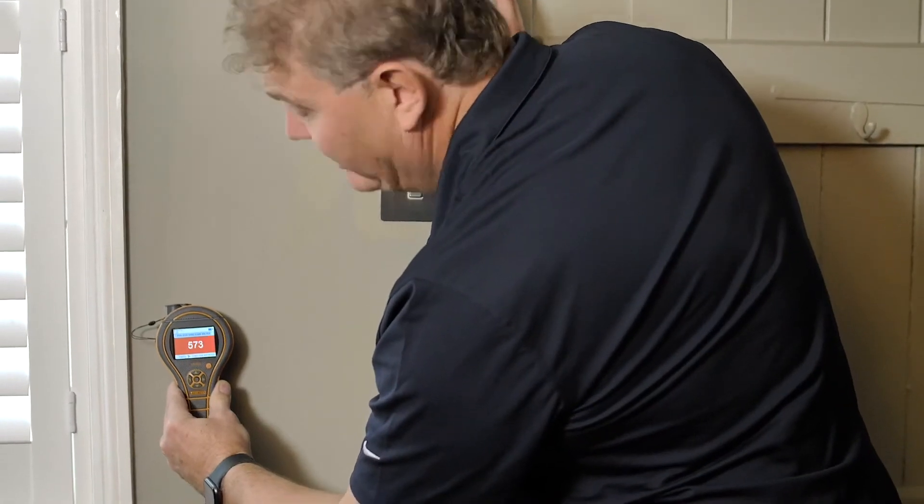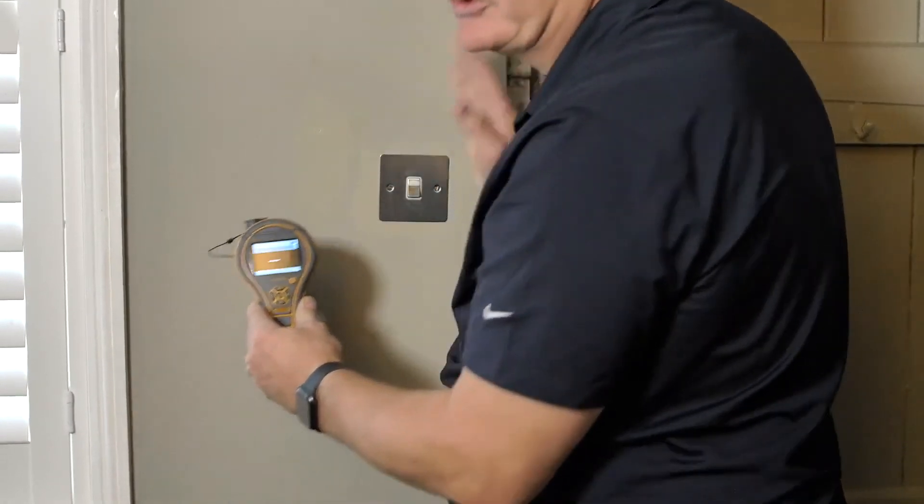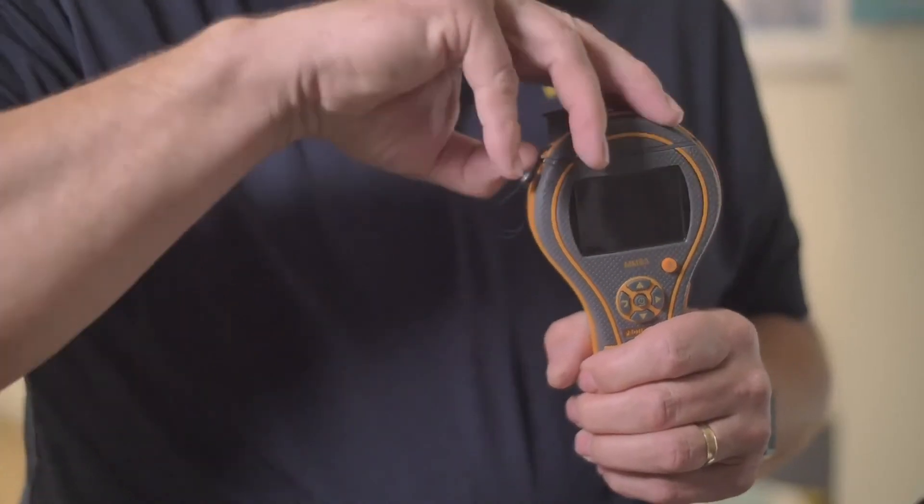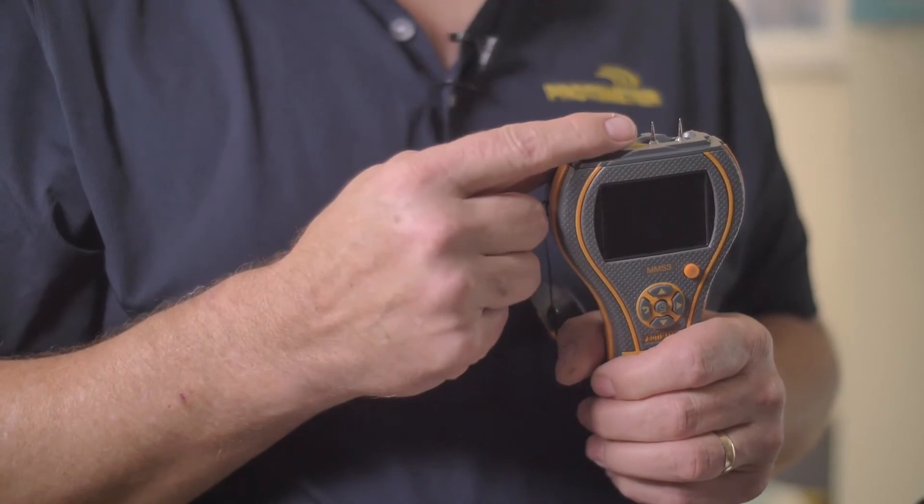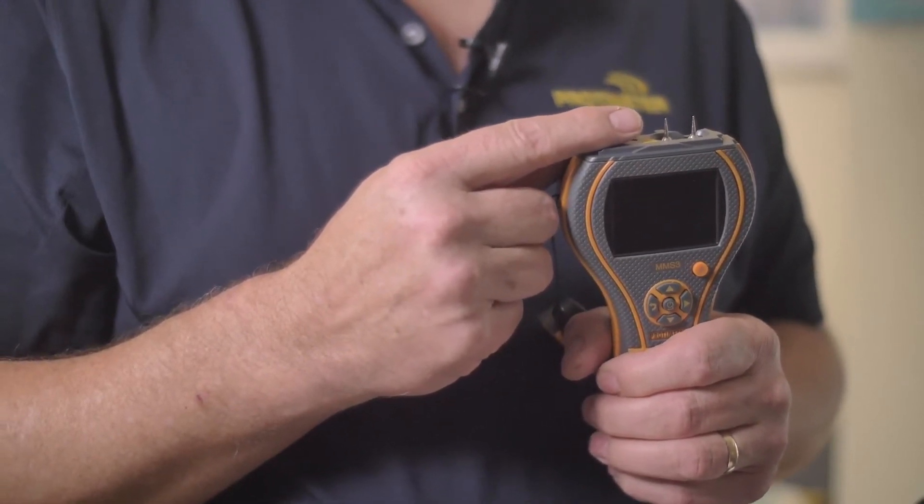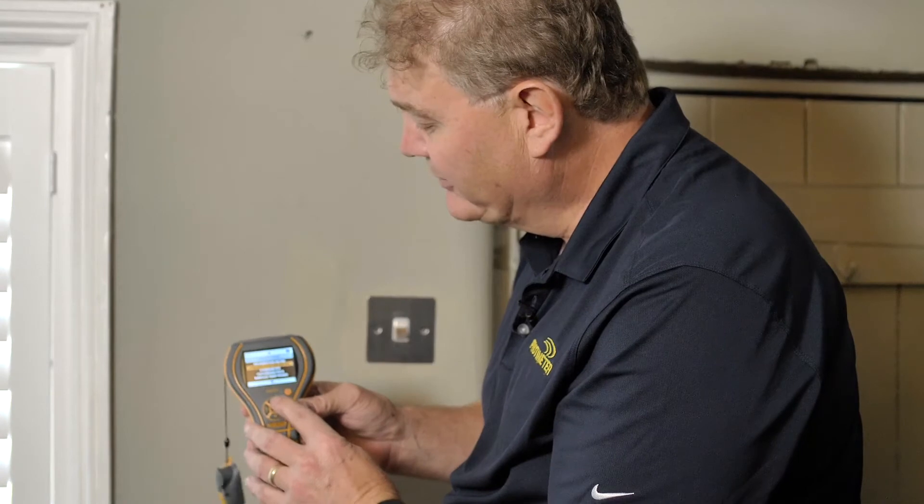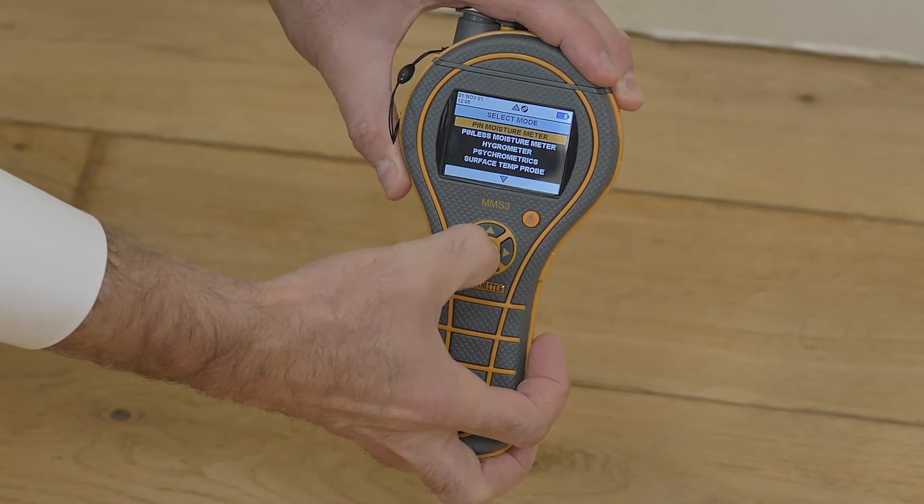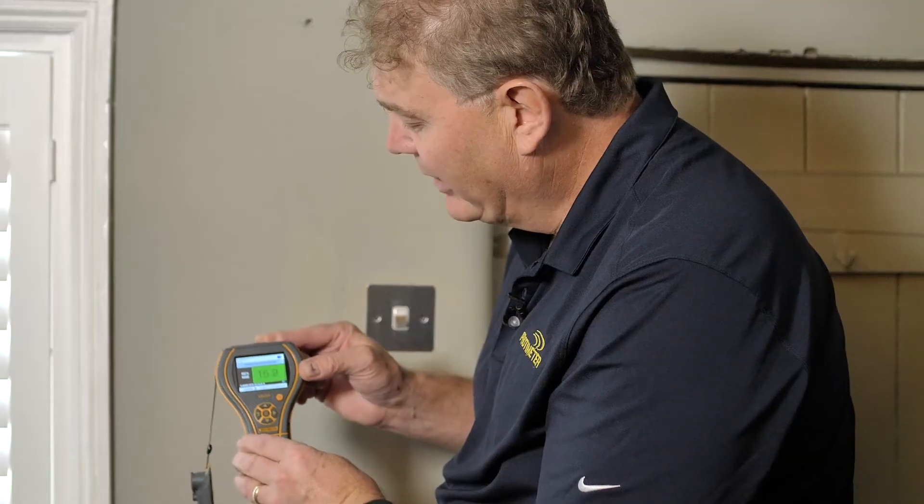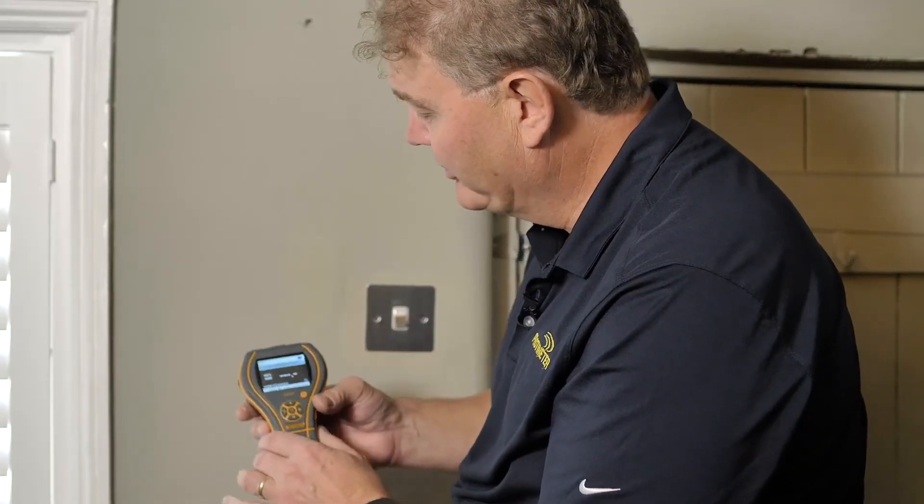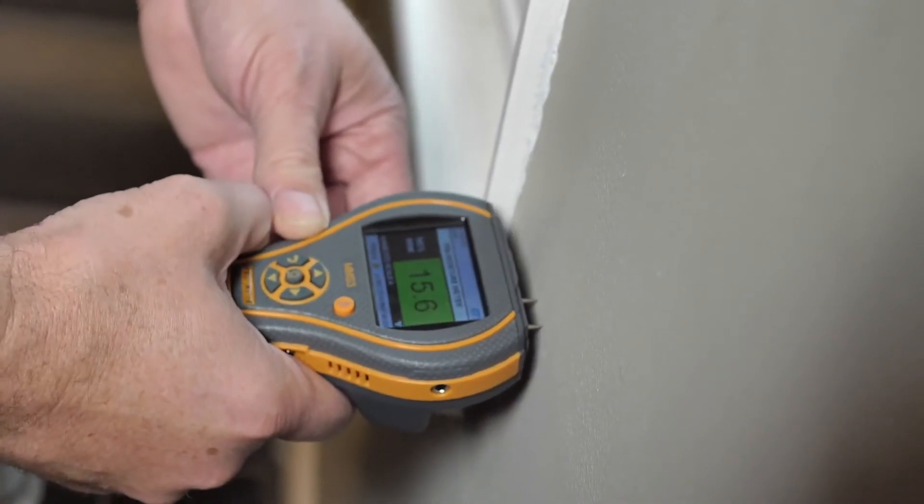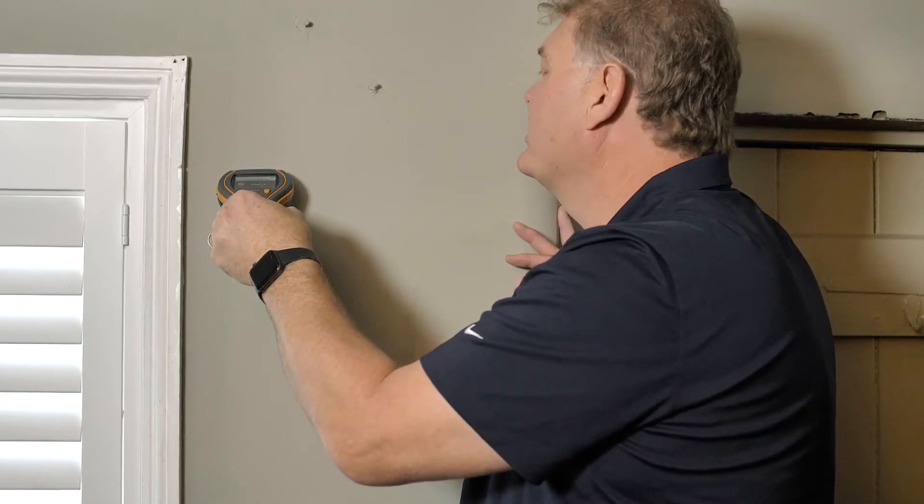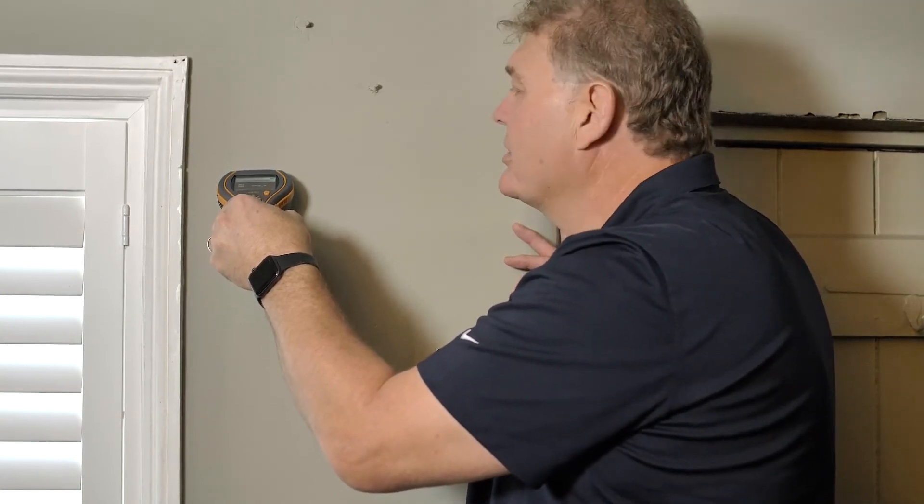What I would do now is confirm the presence of moisture using the PIN function. I would always use the PIN function to record actual moisture readings or wood moisture equivalent readings. To go to the PIN function, we just simply go back in the menu up to PIN moisture meter, and now we have the PIN mode. Again, you can see the green, yellow, and red as we move through the moisture measurement. It's important when you're taking moisture readings on the wall that you just break the surface, and this applies to both plaster construction and drywall.